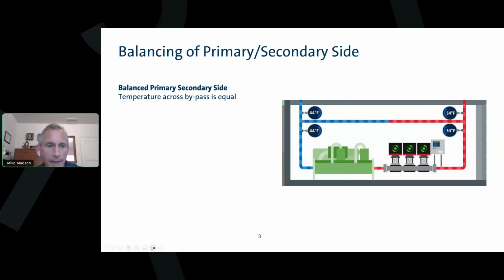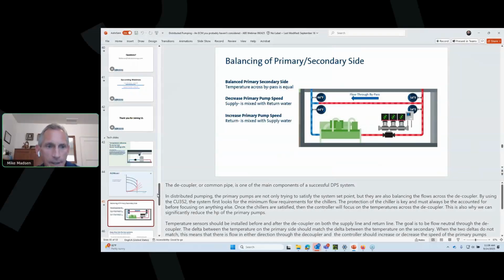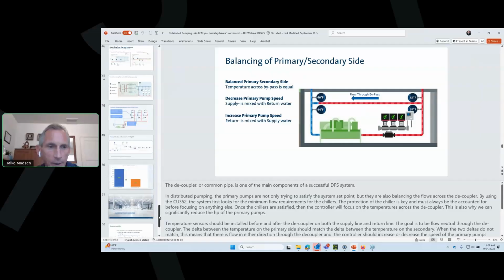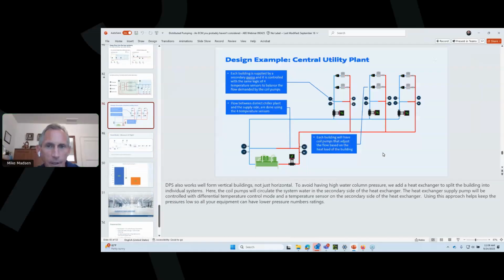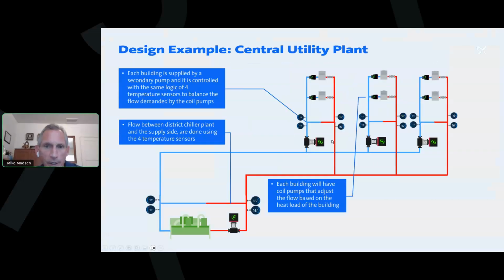So kind of like the plant or the district loop we looked at? Yeah, I think so too, right? So again, if we have heat exchangers in each building, we could do each building slowly over time. But if we don't have heat exchangers, you've got to decouple your primary pumps. If you don't decouple your primary pumps, what happens is, remember, these are high head pumps. These pumps have enough head to serve this furthest zone.